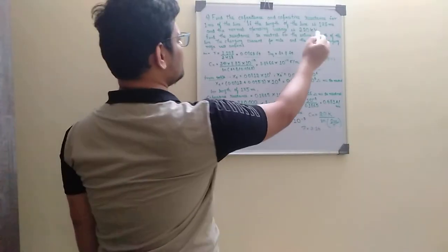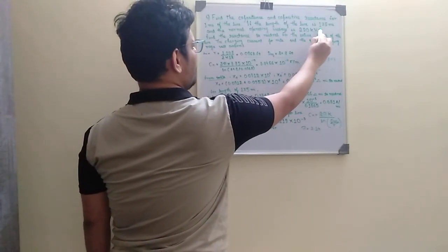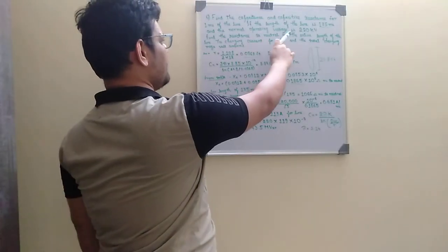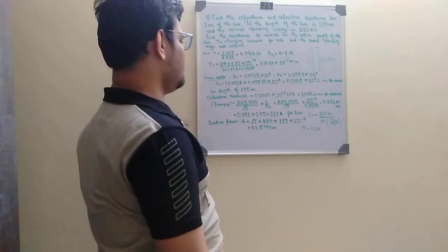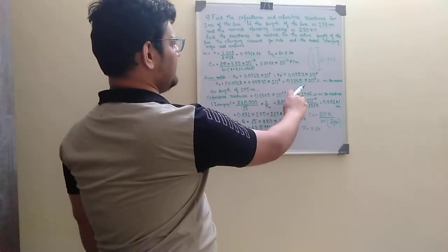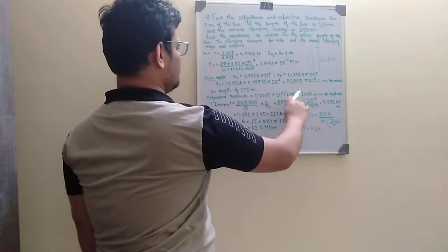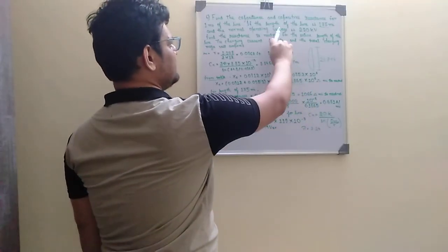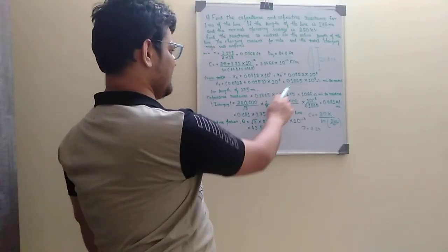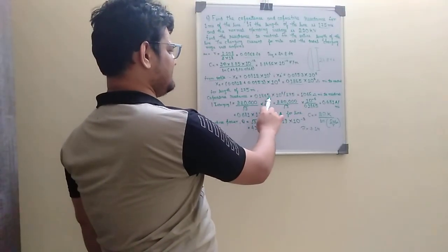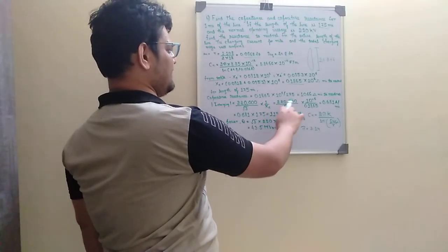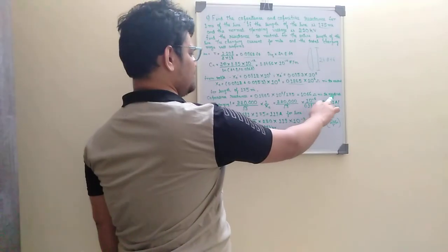Here we have the question: if the length of the wire is 175 mi and the normal operating voltage is 220 kilovolt. In this case, we have to just divide this value. This is for the whole wire, so we will calculate for the 175 mi length of the wire. We divide 0.1865 into 10 to the power 6 by 175. If we divide, we will get 1066 ohm mi to neutral.